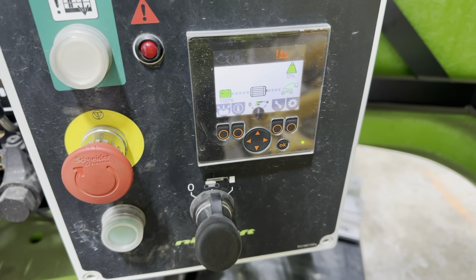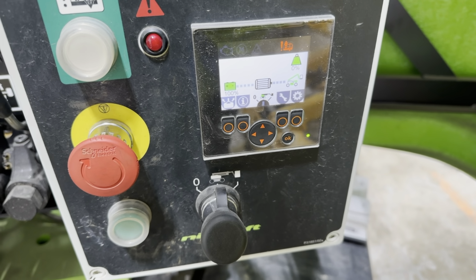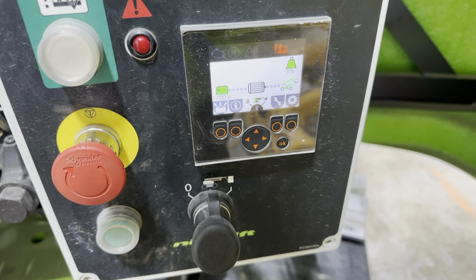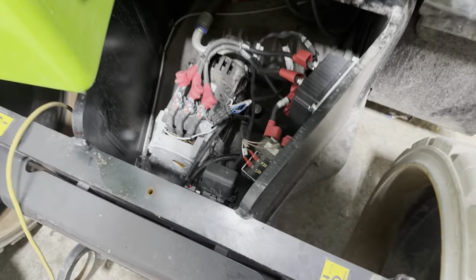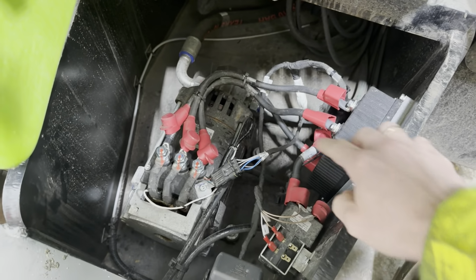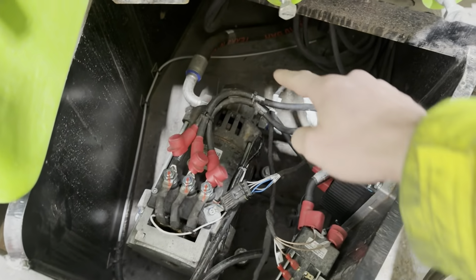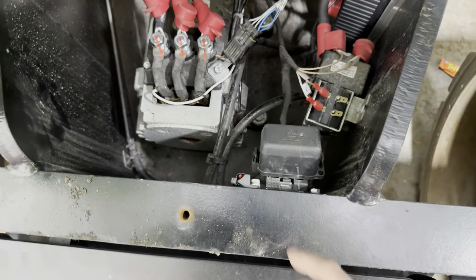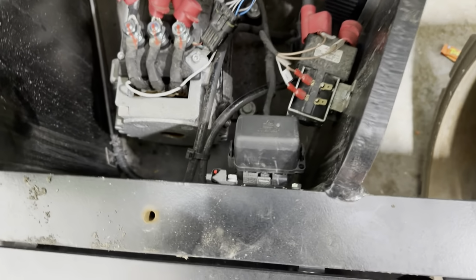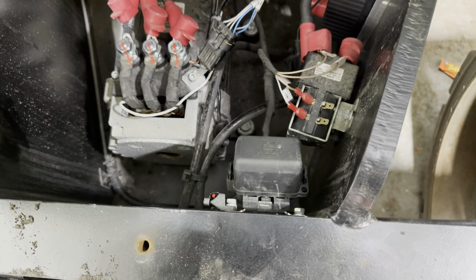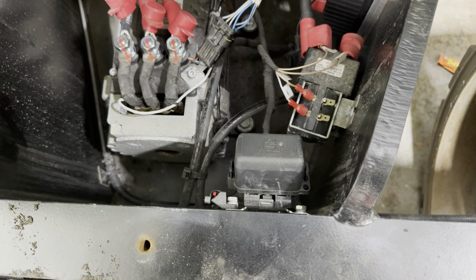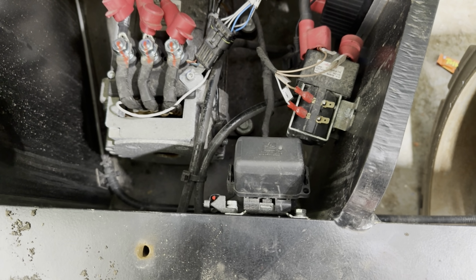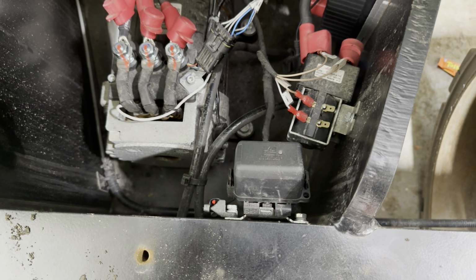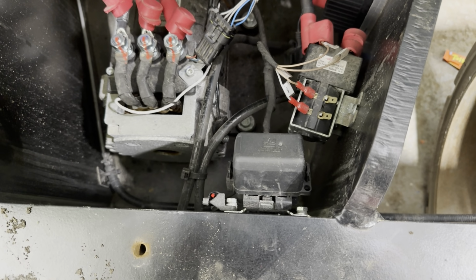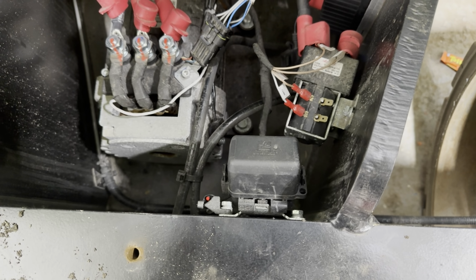So I will try to see on the motor controller if there are any flash codes. That's where my motor assembly is. We have a motor controller on the side, the motor with a hydraulic pump, and the status LED. Normally that LED would flash error codes. If the controller has no error codes, the display flashes 1-1, which is the status flash, as it is now. So it seems like there are no error codes, just 1-1.